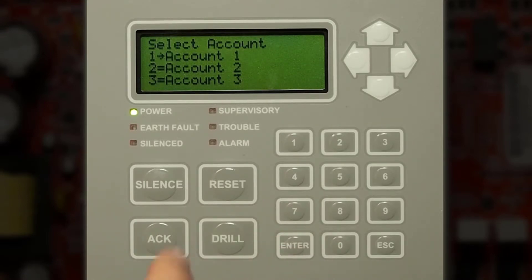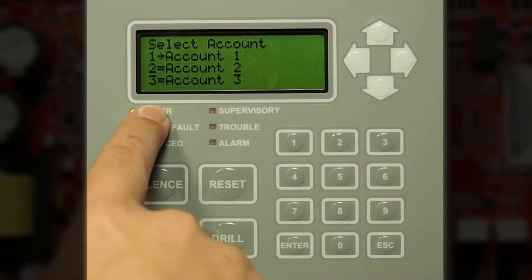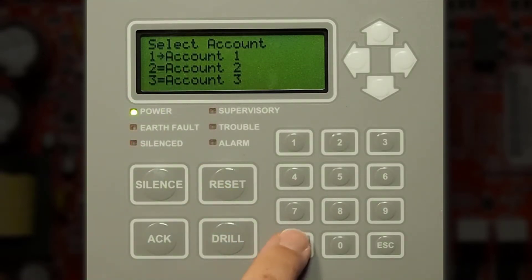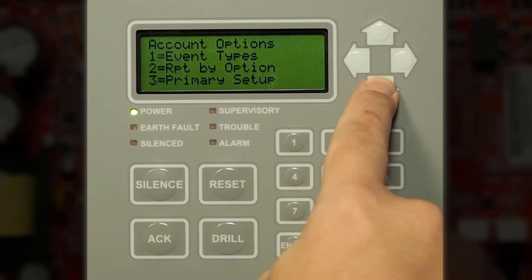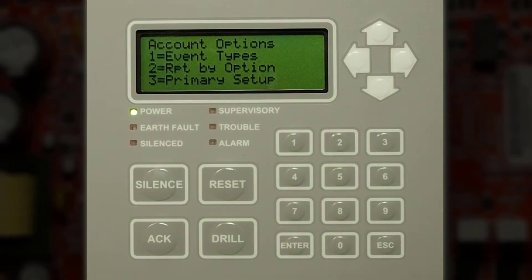Press enter, you can have up to five accounts for the dialer. Press enter on account number one. You can choose what event types to send to the central station such as alarm, trouble, or supervisory. You can report by panel, zone, or point — panel being general signals, zone is by software zone, and point is by specific point.